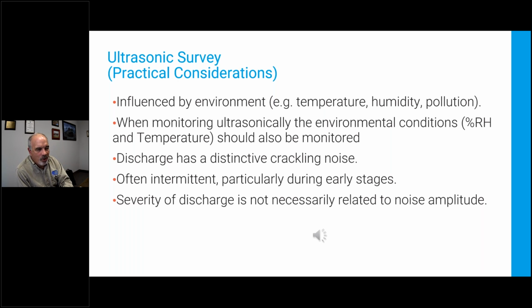So we don't know where this discharge is occurring. Is it on the front of the switchgear? Is it on the back? Is it behind the panel? Is it buried? It can vary. But wherever it's located isn't going to change over time. So let's track it over time. Or if I've got 6 different cabinets that are all built exactly the same, and I've got one level that's a lot higher on one than the other 5, that's trending or comparing to other things. So we want to do that.